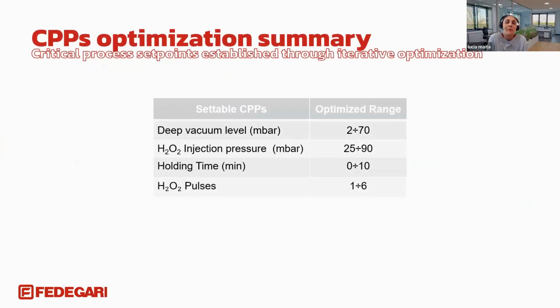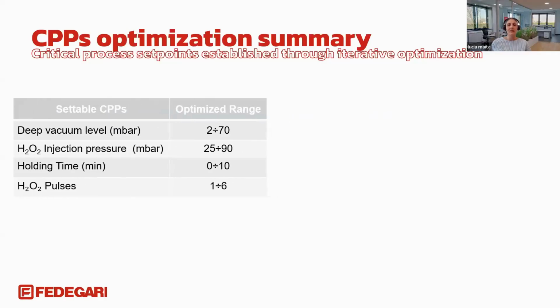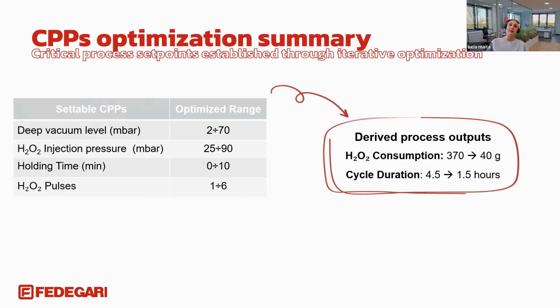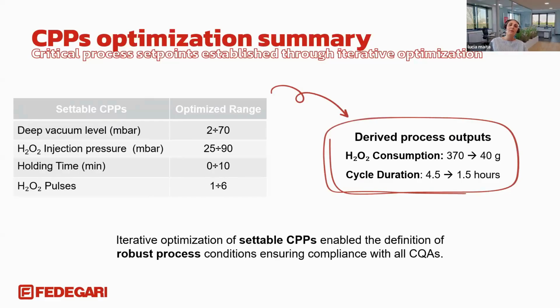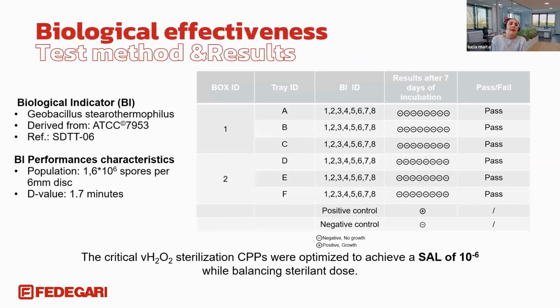The process was optimized by adjusting the key parameters such as the vacuum level, the H2O2 injection pressure, the holding time, and the number of pulses. This iterative approach allows us to progressively improve the process performance. As a result, we can summarize that both hydrogen peroxide consumption and the overall duration of the cycle, so the cycle time, were significantly reduced while maintaining the process robustness.